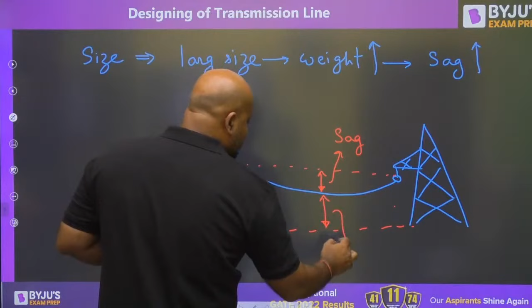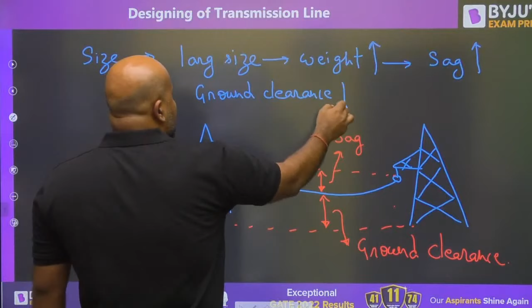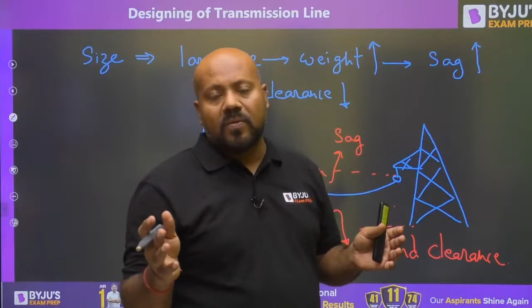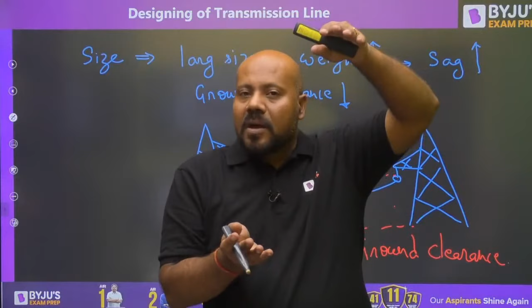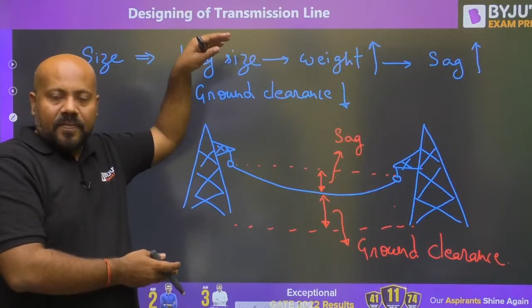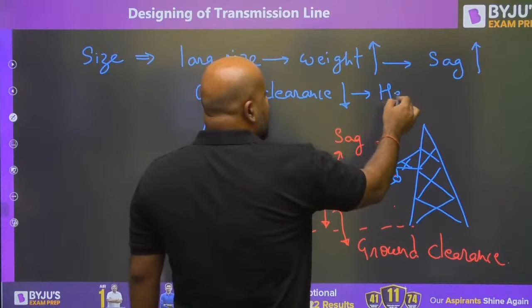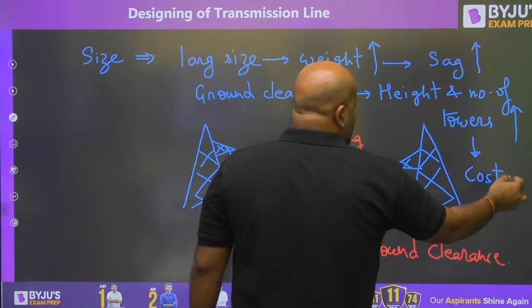Very obviously, when the weight is very high, the sag in the transmission line conductor is going to be very large. When the sag is large, the ground clearance is going to be less. But when operating at such high voltage levels, like 400 kilovolts, 765 kilovolts, 1200 kilovolts, there should be a minimum ground clearance. In order to maintain this, you have to increase the height of the tower, and also the number of transmission towers. So the overall cost of setting up your transmission system is going to increase.